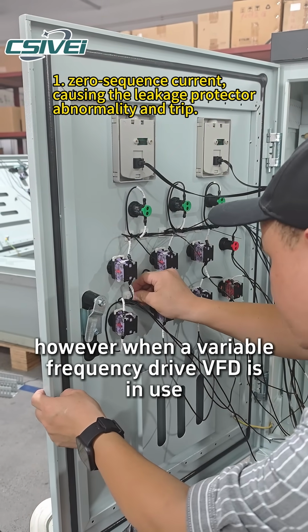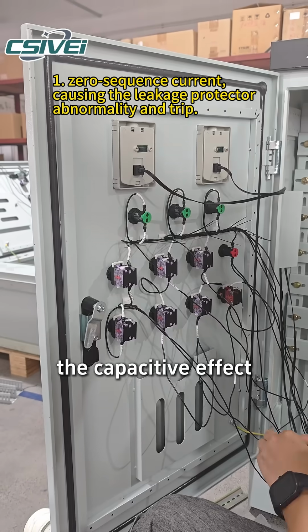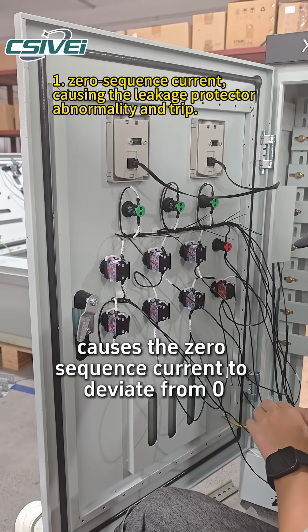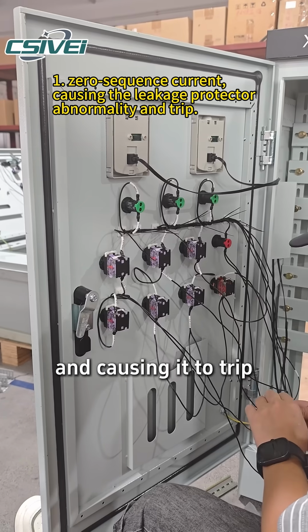However, when a variable frequency drive (VFD) is in use, the capacitive effect causes the zero sequence current to deviate from zero, frequently triggering the protection mechanism and causing it to trip.